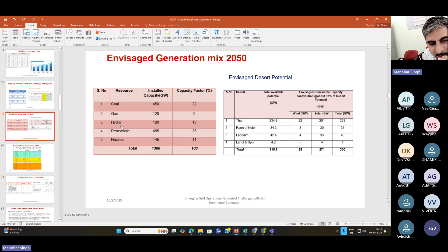This 70 gigawatt, from where can I get it? I can't get this 70 gigawatt from the governor of these machines. How much can the governor support me? 5%, 10% is 45. 5% is only 22 gigawatt. So that gap will be out from this governor. And other machines have no governor, they don't have a governor here.